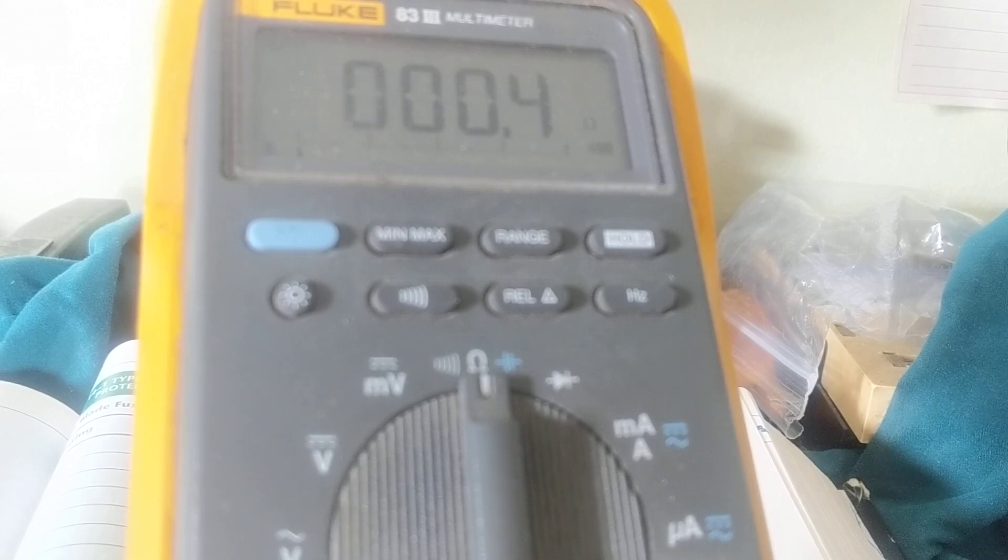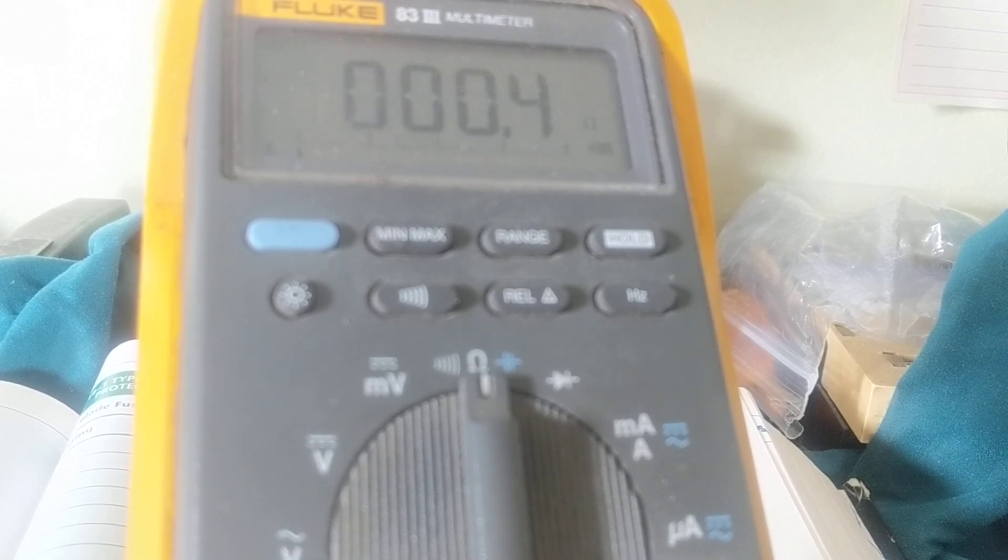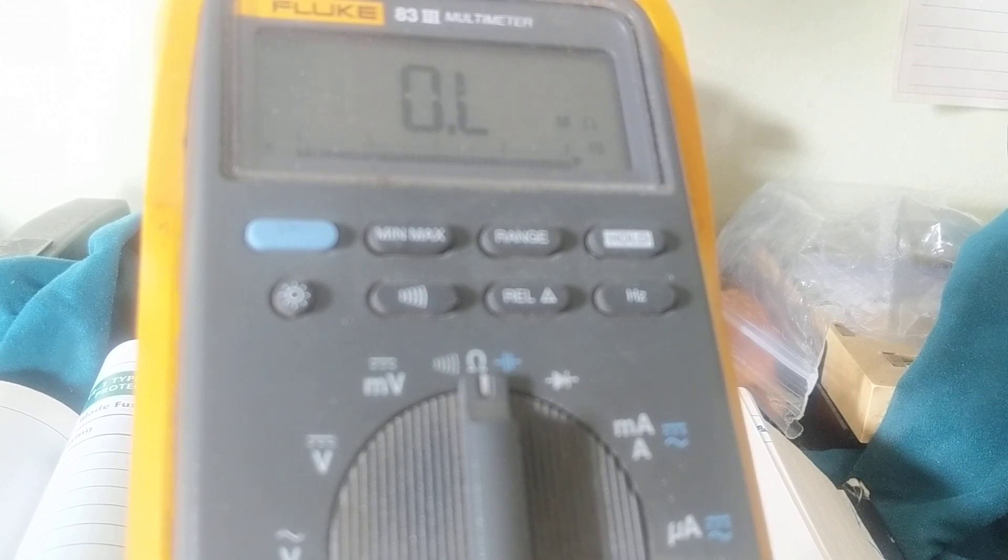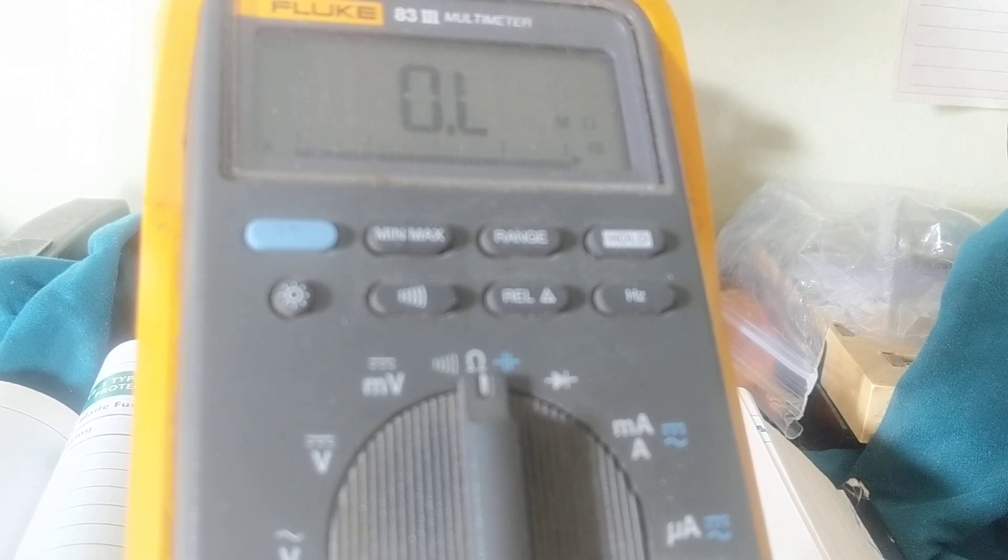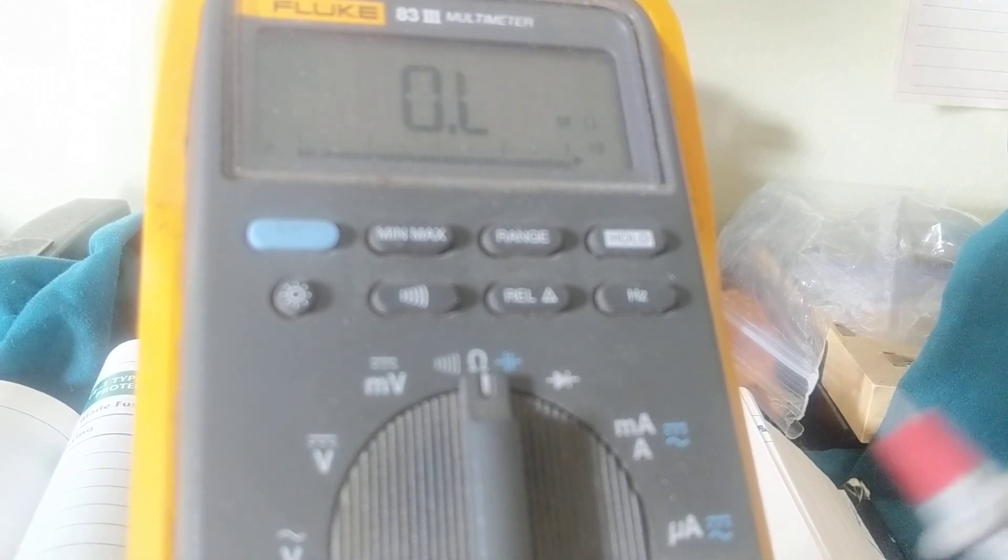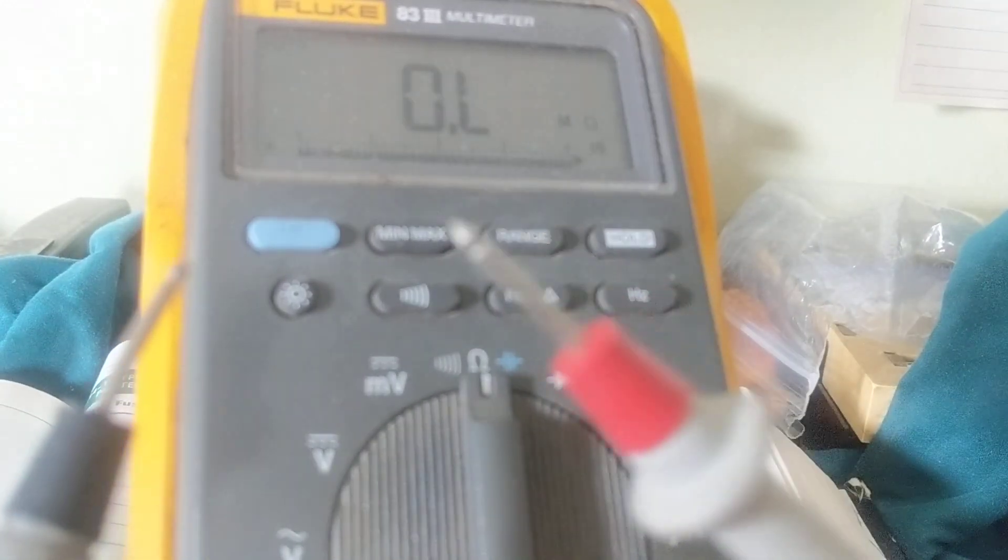0.4, 0.3 ohms as you see. Always. Why? Not because of a battery being weak, but because the leads, these leads sometimes they're broken. If they're broken, you will not get an accurate reading for ohms, for DC volts, for AC volts. First thing, always measure continuity when you grab that meter.